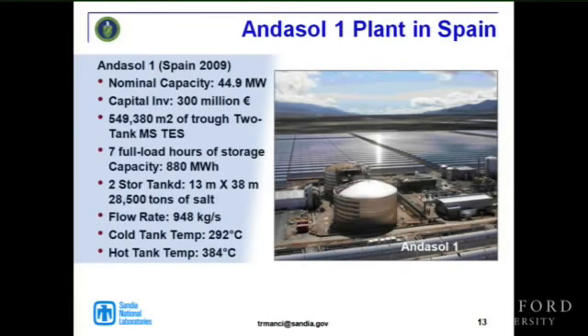They have thermal energy storage in the form of a two-tank molten salt system using a sodium potassium nitrate salt, about 28,500 tons of it, giving seven full load hours of storage. They went to this because they could, and because it increases the revenues from the plant more than it costs to put it in.